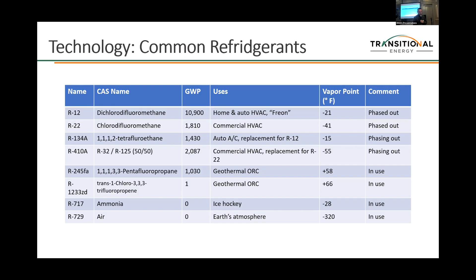Geothermal technology wouldn't be geothermal technology without heat exchangers. In organic, binary cycle systems, you do need heat exchangers because you've got to get that heat into the closed loop refrigerant inside the box. With a steam or dry steam application, you tend to not need this because either the steam is directly spinning the turbine or it's going through a flash cycle.